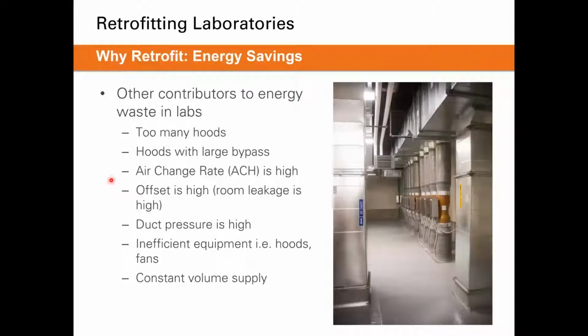And then air change rate. If the air change rate is set too high unnecessarily, then that would also lead to wasted energy in labs. If your offset is too high in the room, that would indicate that your room has a high leakage rate. So you can go in and touch up the space as much as possible in order to try and decrease your required offset to maintain that safe pressurization.